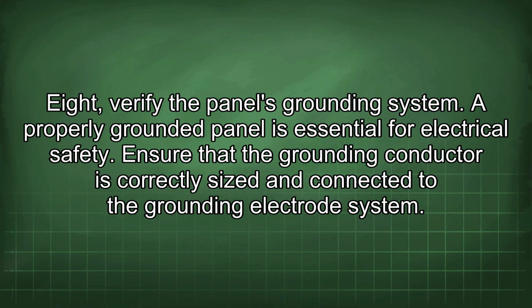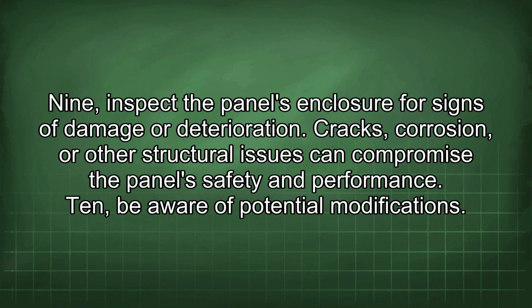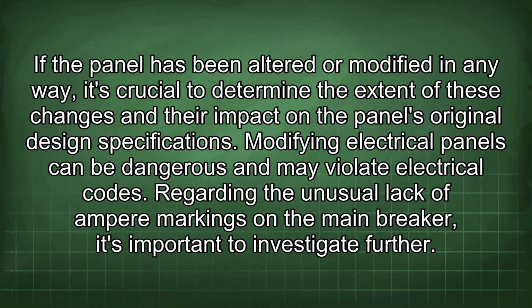8. Verify the panel's grounding system. A properly grounded panel is essential for electrical safety. Ensure that the grounding conductor is correctly sized and connected to the grounding electrode system. 9. Inspect the panel's enclosure for signs of damage or deterioration. Cracks, corrosion, or other structural issues can compromise the panel's safety and performance. 10. Be aware of potential modifications. If the panel has been altered or modified in any way, it's crucial to determine the extent of these changes and their impact on the panel's original design specifications. Modifying electrical panels can be dangerous and may violate electrical codes.